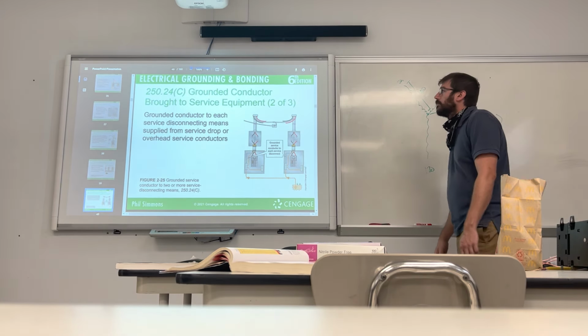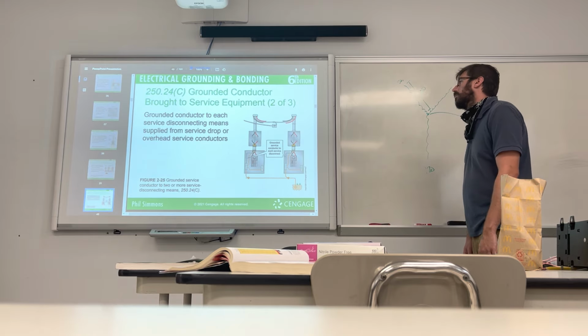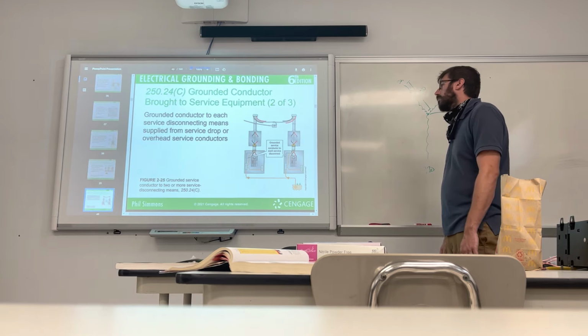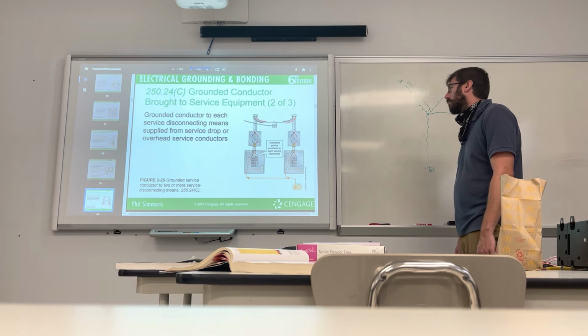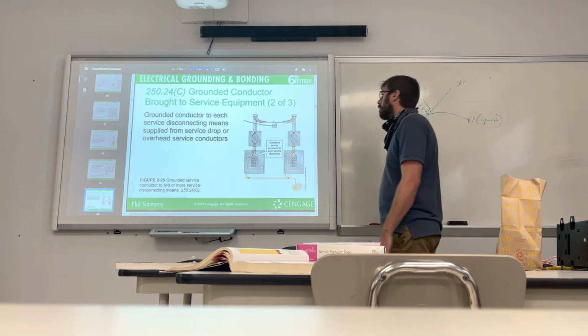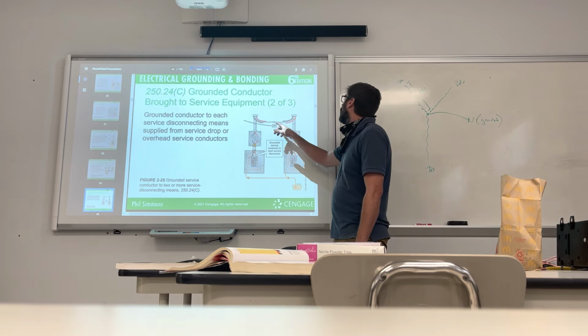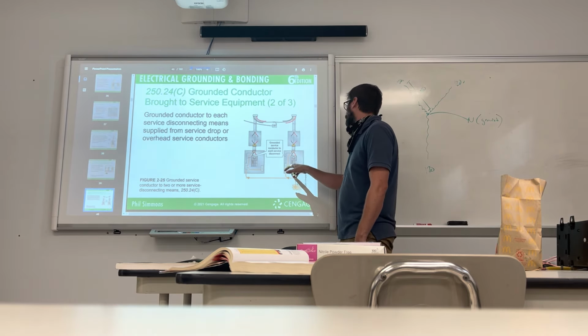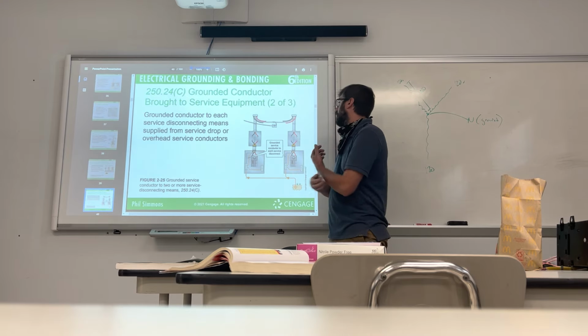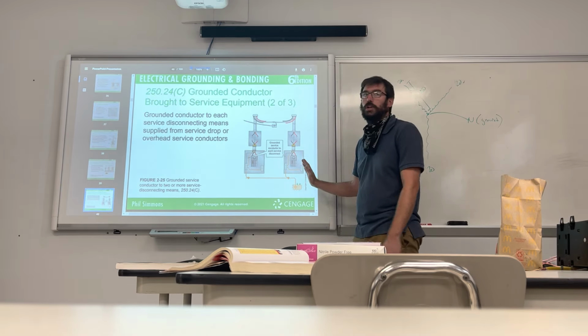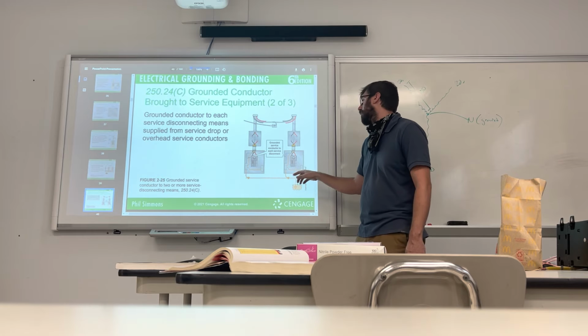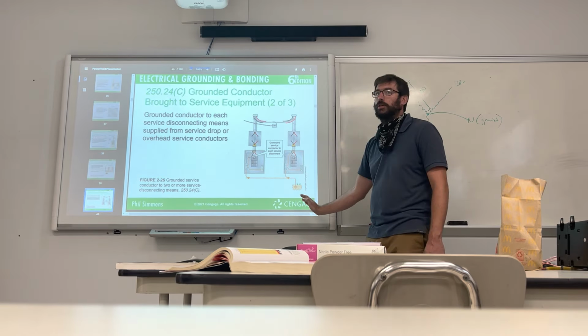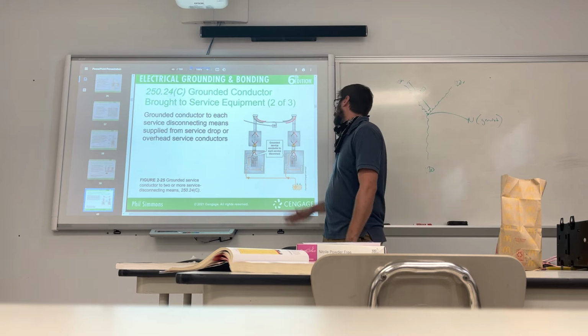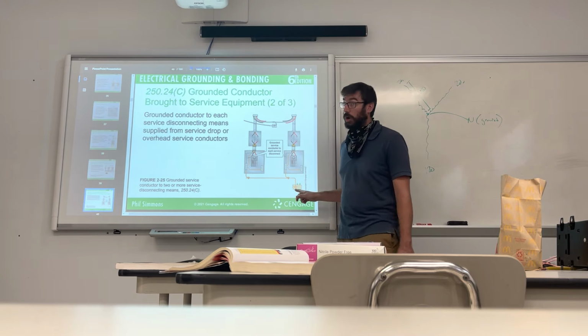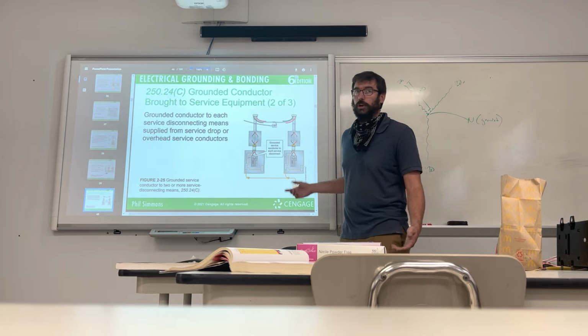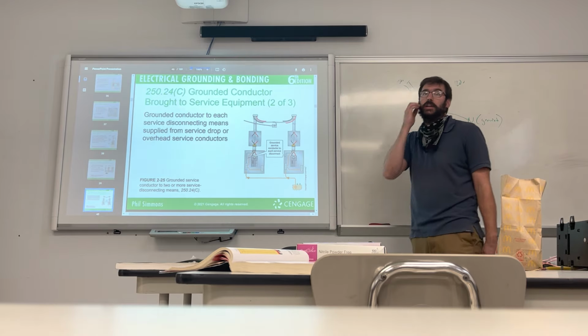Grounded conductor brought to service equipment. Grounded conductor to each service disconnecting means supplied from service drop or overhead service conductors. So it's a common neutral there, it comes down, it's grounded and bonded in the mains. Like I said, these are two separate meters, so these both get an even shot at power. So we consider both of these to be mains, but they're bonded and done accordingly. Now, if this is 100 amps and this was 100 amps, you would have to size this for 200 amps, the maximum amount of power that can ever be taken.